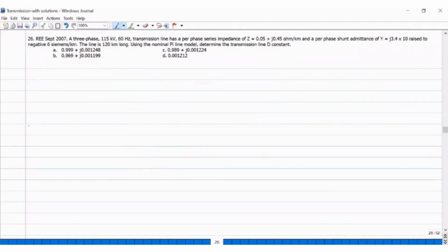A three-phase 115 kV, 60 Hz transmission line has per phase series impedance of 0.05 plus j0.45 ohm per kilometer and a per phase shunt admittance of j3.4 times 10 to the negative 6 Siemens per kilometer. The line is 120 kilometers long. Using the nominal pi line model, determine the transmission line D constant.